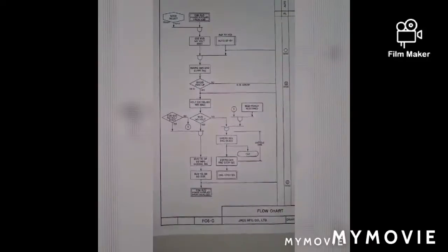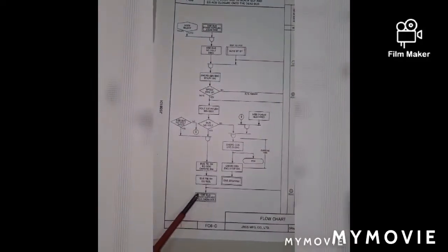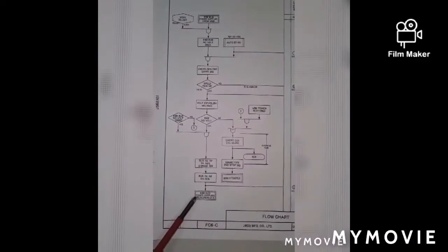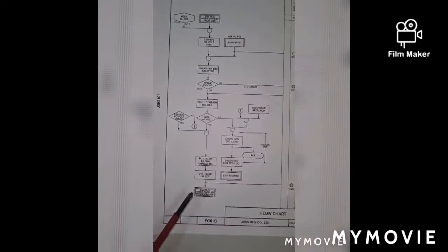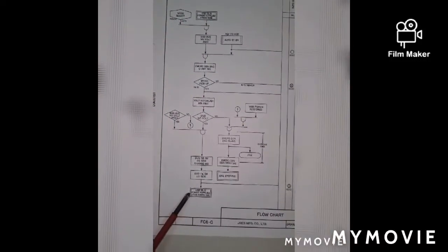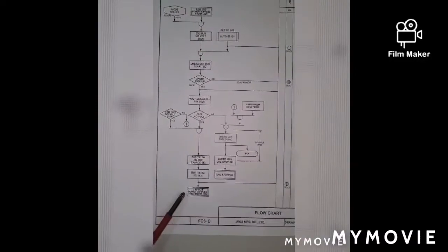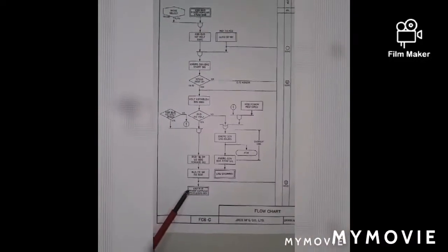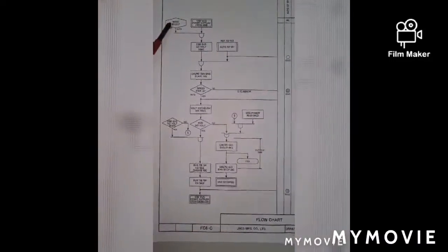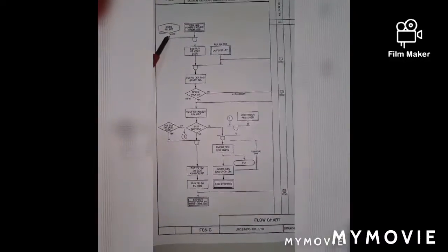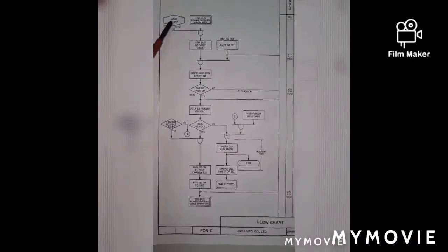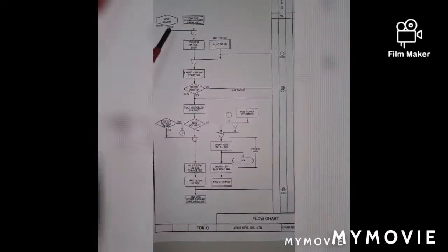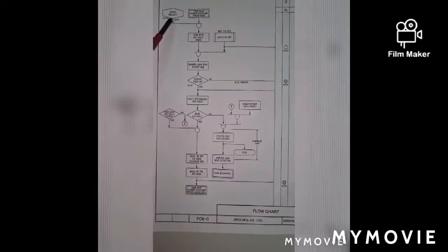And on the upper part, there is also a final condition. The final condition we want to do is to supply the power on the emergency switchboard coming from the emergency generator, caused by a power blackout. Here is the preparation. You must push the selector switch mode into automatic. This process flow goes this way.